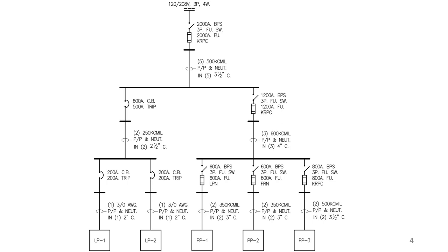Another way we help our customers save money a lot of times is series rating. And I'm sure this is news to none of you guys. Series rating allows me to use a lower AIC rated device. And of course, when I have series rating, I completely lose the selectivity. But if I don't need it, I don't care. What the series rating also does is, of course, it reduces the arc flash hazard.